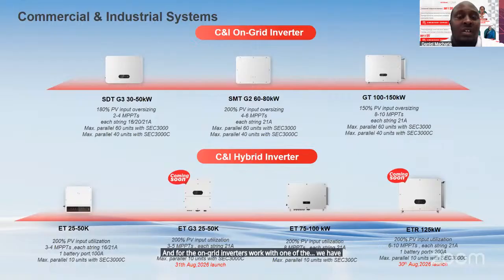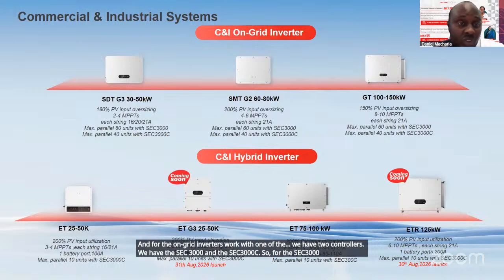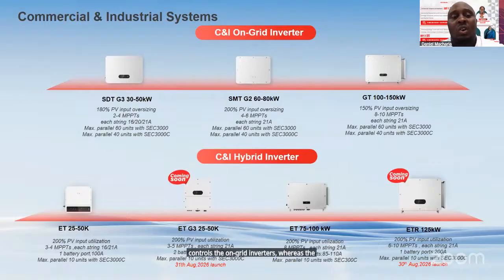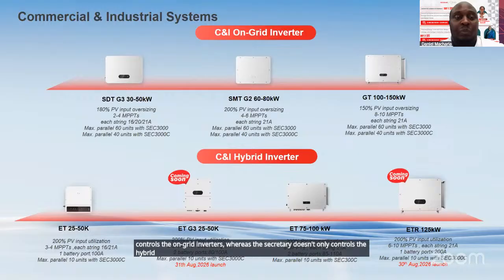And for the on-grid inverters, we have two controllers. We have the SEC 3000 and the SEC 3000C. The SEC 3000 controls the on-grid inverters, whereas the SEC 3000C only controls the hybrid and the grid type. So the SEC 3000 cannot control the hybrid inverter. So if you have hybrid inverters, you need the SEC 3000C.